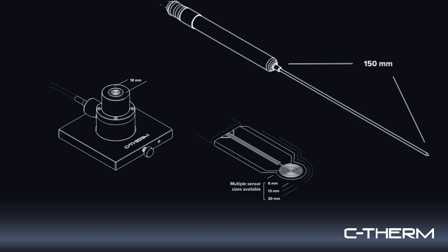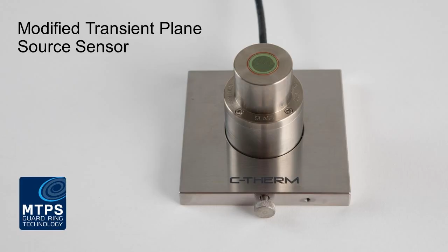You'll notice some different temperature ranges, the precision statements, the accuracy, and some of the different industry ASTM and ISO methods associated with these techniques. So that gives you a good overview of the capabilities there. So this is a picture of what an MTPS sensor looks like. To detail a little further, the active area is that green area in there. The red is a room temperature vulcanized silicone that forms a liquid seal on the sensor. That makes it very appropriate for testing liquids, gels, semi-solids, powders, etc., as well as, of course, solid material.